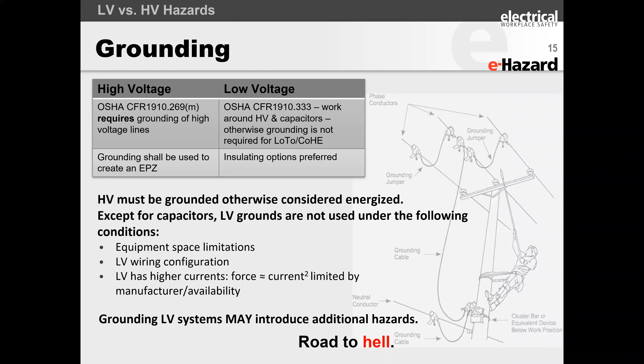Okay, so let's talk a little bit more about equipotential zones, right? So remember I told you previously V2 minus V1 is equal to 0, right? The idea is we want you all to float together, right? Like Pennywise famously saying, down here, we all float, they all float, Georgie. All right, so when you've got this high voltage line, we actually want the entire system to increase and decrease, right? So if you have 1,000,000 volts coming through that line, we want the worker to jump up to 1,000,000 volts with that line. Okay, folks, 1,000,000 minus 1,000,000 is still 0. That is how high voltage folks create safety.